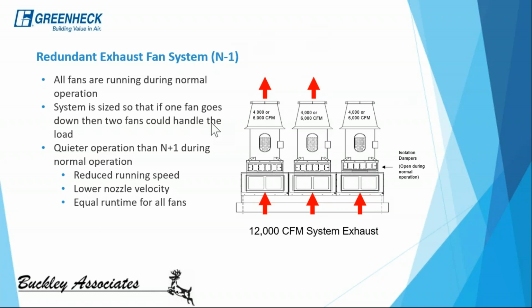Okay, the reason we're starting to see N-1 quite a bit is that these fans are always going to be running at constant speed and lower speeds. So this means a lower nozzle velocity, quieter operation, less power, and equal runtime for all the fans. So there are benefits to both of these redundant scenarios, both N-1 and N+1. However, it's usually up to the owners how they want to operate or which scenario they prefer.